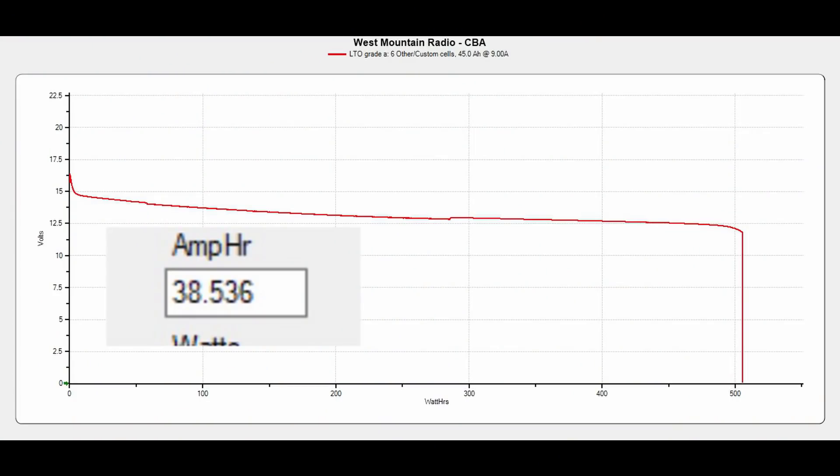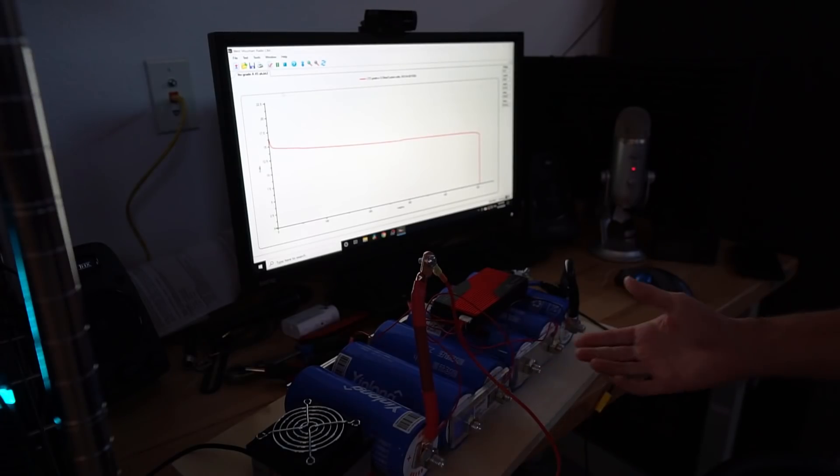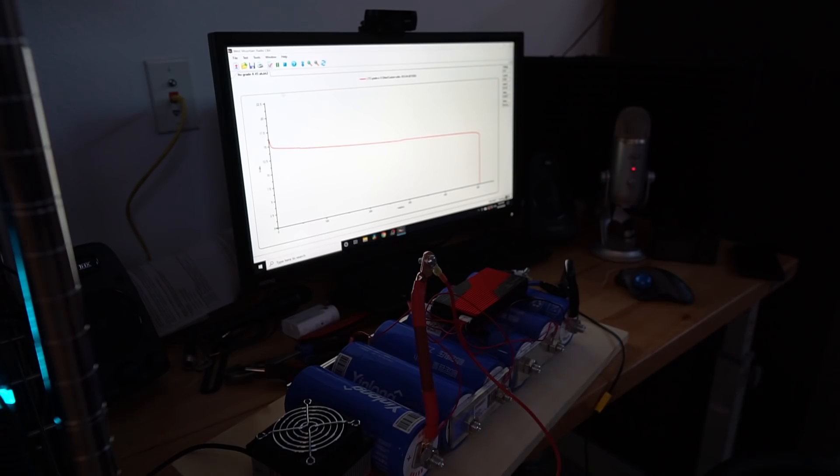Uh-oh. We only pulled 38 amp hours. That is not good. We're at 2.1 volts per cell and everything looks fine. So that's not good. These might be grade B cells.